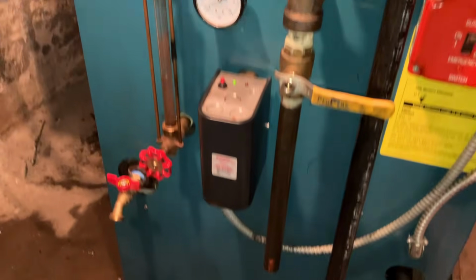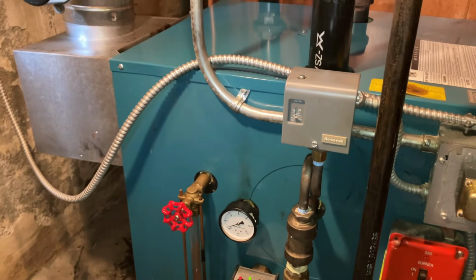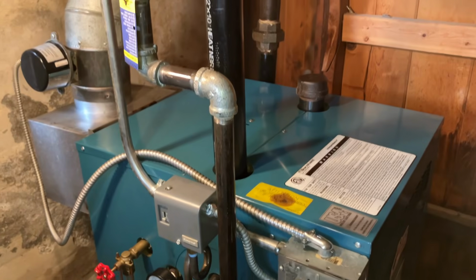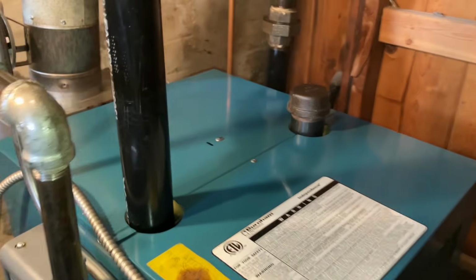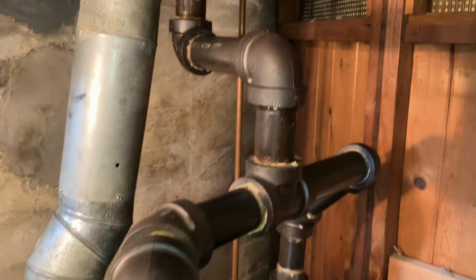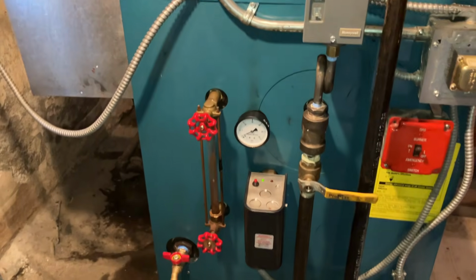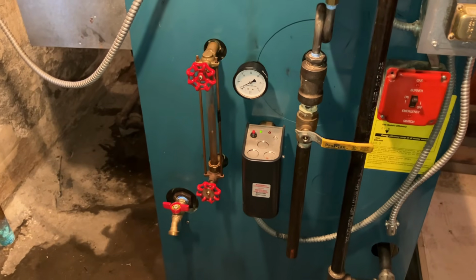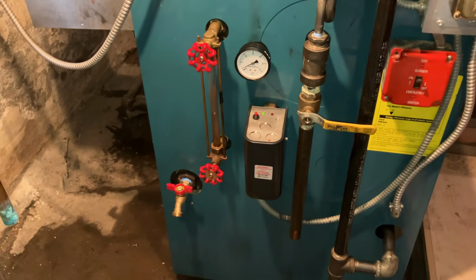All right, everything is clean. Everything is documented. Got all the debris off the jacket of the boiler. Come on, we're professionals. Look how nice and clean that is. Even the piping is nice and clean. We're going to fill up the boiler. We're going to test the low water cutoff, make sure that's fully operational.